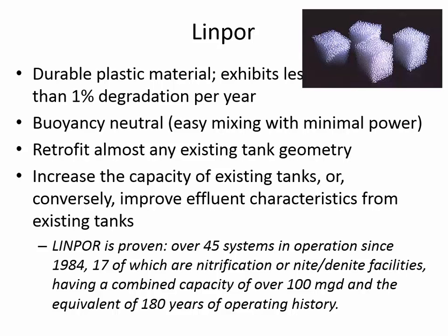It's buoyancy neutral, meaning that it has the same density as water, which makes it easy to mix the Linpor through the aeration basin, and you don't have to put a lot of mechanical energy into keeping them suspended. And it's easy to retrofit an existing aeration basin just by putting these in, and you have to configure a screen so that they stay in place and don't go out of the aeration basin. So it can be used to increase the capacity or improve the effluent characteristics.